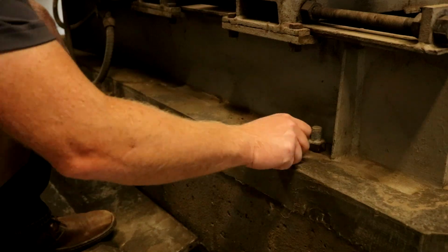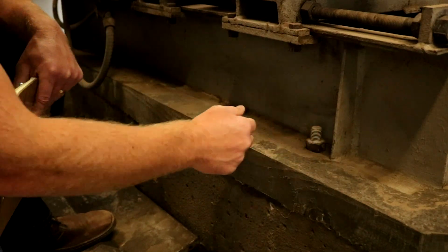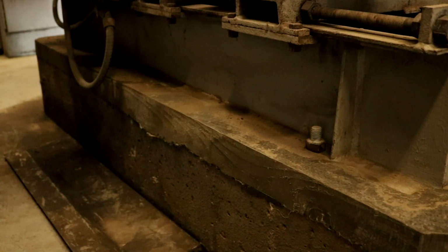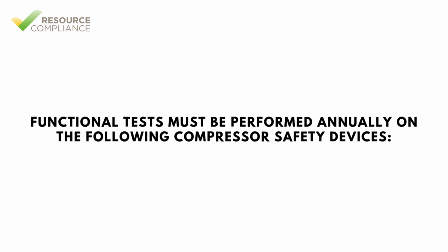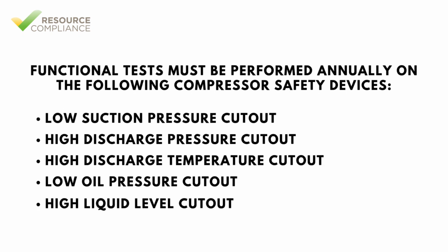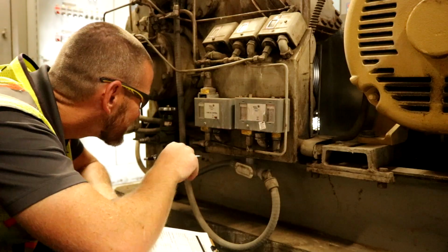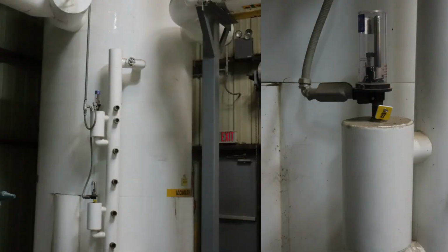Annually, compressors must be inspected for proper anchorage, surface corrosion, drive alignment, and unloader operation. Functional tests must be performed annually on the following compressor safety devices: low suction pressure cutout, high discharge pressure cutout, high discharge temperature cutout, low oil pressure cutout, and high liquid level cutout.